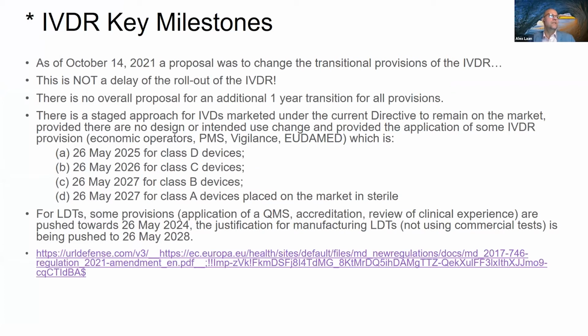I think it's good to see that the rollout of the date of application for existing devices under the IVD directive has been smeared out a little bit. So there's more grace period, also depending on the class. If you have a higher class, the real due date will be 26th of May 2025. Whereas for class A devices placed on the market in a sterile state, this is the 26th of May 2027. And for laboratory developed tests, it may even be pushed out to 26th of May 2028.